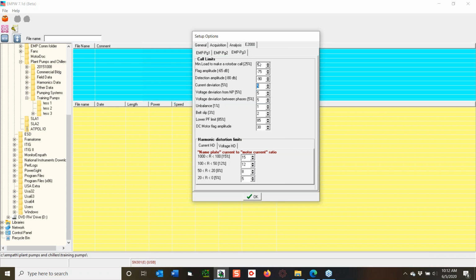I've got very sharp peaks, and I have frequently gone in after a motor's been repaired, sitting on a test bench, disconnected regardless of size, and been able to determine if I've got rotor issues. That's primarily what that's for. It's because you need peaks to separate away from other peaks. And then the flag amplitude, I set down a little bit lower and detection down a little lower. So it will tend to flag me things earlier than intended.